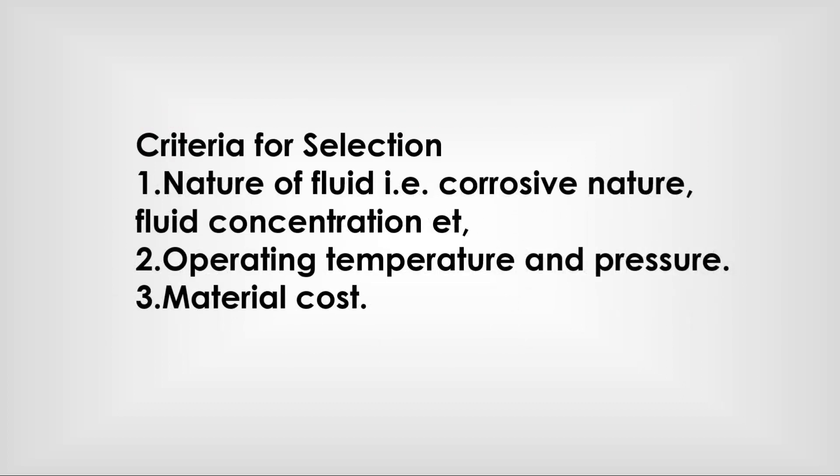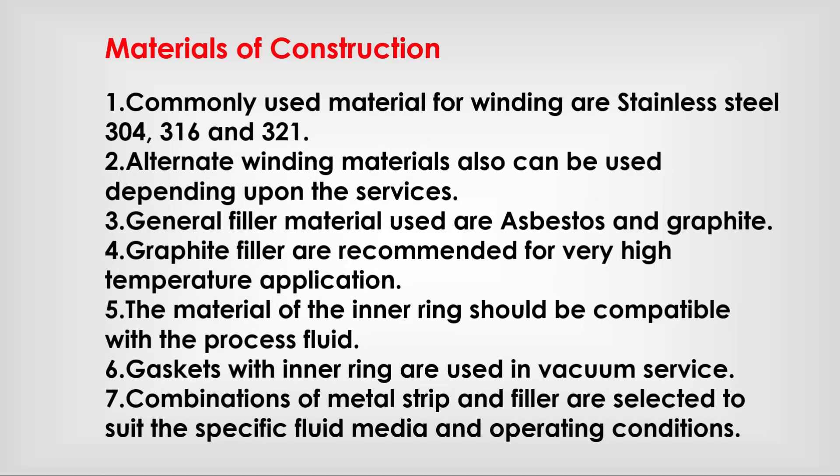Criteria for selection include the nature of the fluid (e.g., concentration), operating temperature and pressure, and material cost. Commonly used winding materials are stainless steel 304, 316, and 321. Alternate winding materials can also be used depending upon the service.